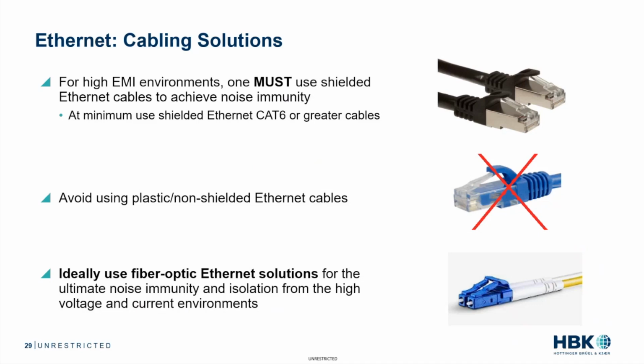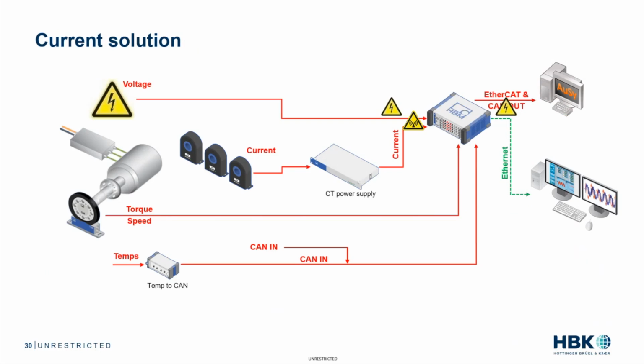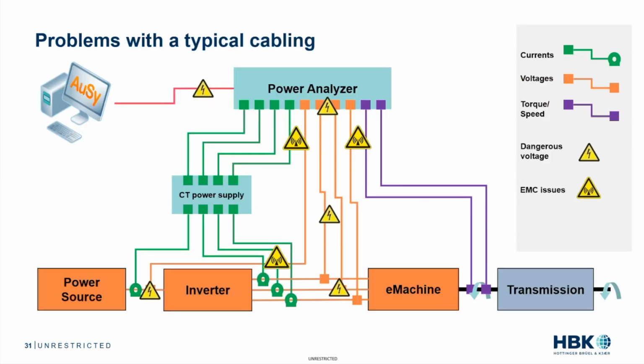But ideally, you would want to use a fiber optic Ethernet solution, so that has the ultimate noise immunity and isolation from high voltage and the current environments. So let's go back to this solution we were looking at for a typical powertrain measurement. So we have the high voltages throughout our setup, whether it be at the test point and all the way back to the power analyzer and your test lab. And so here are the problems with a typical setup and the cabling. You've got high voltages everywhere, EMI everywhere, and really the challenge is, how do you mitigate this even after applying all the cabling solutions that we've just looked at here in the last few minutes?